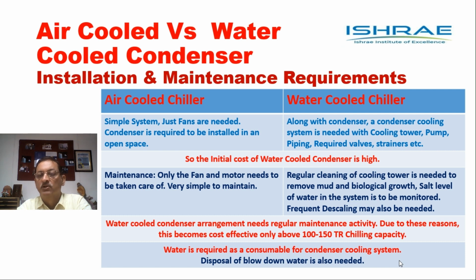Whereas in a water cooled chiller, we need, along with a condenser cooling system, which will have cooling tower, which will have pumps, which will have piping, which will have the required valves, strainers, etc. And so, therefore, to purchase all these equipments and to install them, the cost of installation of a water cooled chiller is much higher as compared to the cost of installation of an air cooled chiller.